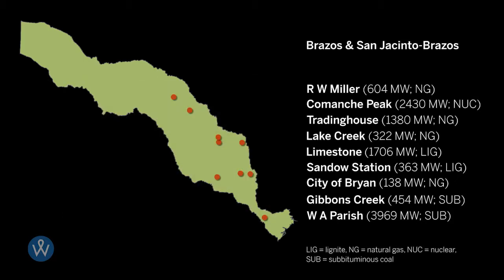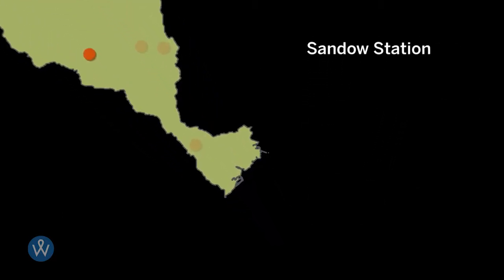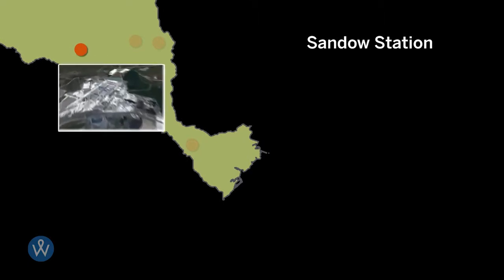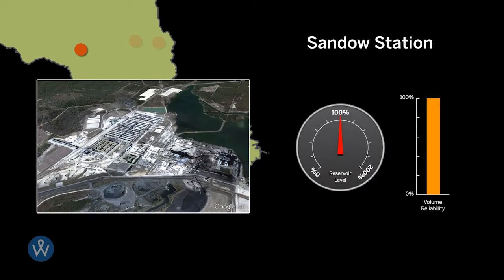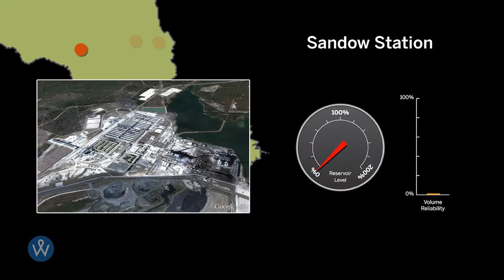Here we'll focus on reliability. The Sandow Generating Station, for example, has reliability of 100 percent with existing levels of storage during the drought of record. When half of the existing reservoir storage is unavailable, reliability falls to 93 percent. When existing reservoir storage is completely dry, reliability falls to 1 percent.